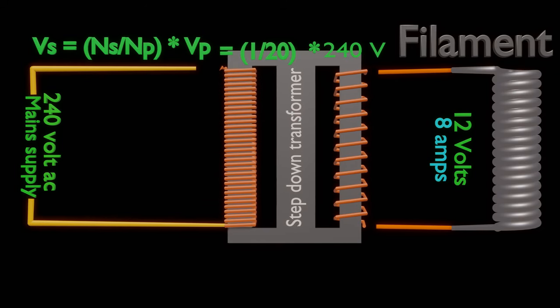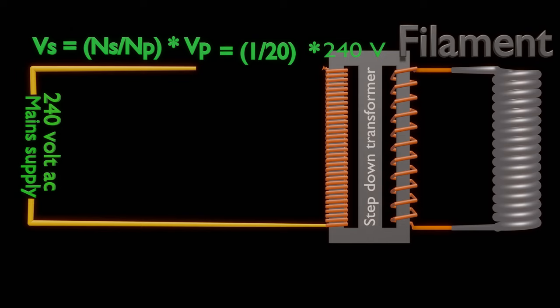Different body sites or diagnostic procedures need different tube current. For different tube current, we need to apply different filament current. To vary current in the filament, we need to vary voltage across secondary of the step-down transformer. But the step-down transformer has fixed turn ratio. The only way to have variable voltage at secondary is to apply variable voltage to its primary. Variation in input voltage to primary is achieved by use of an MA selector.